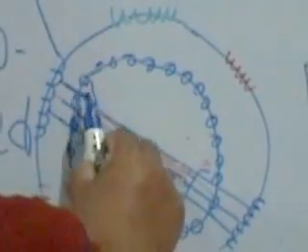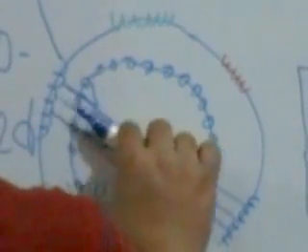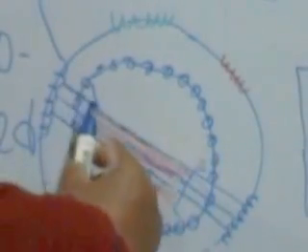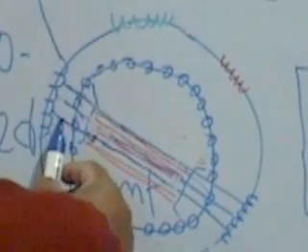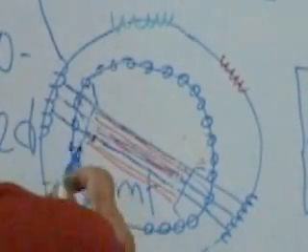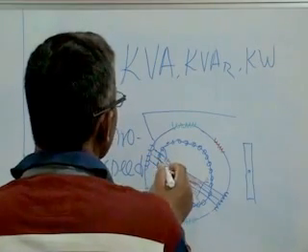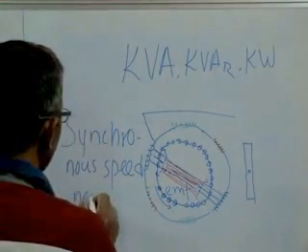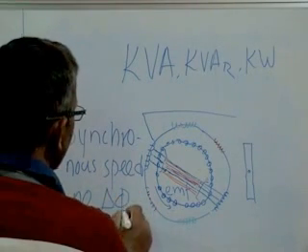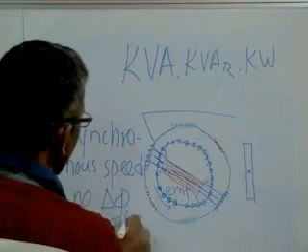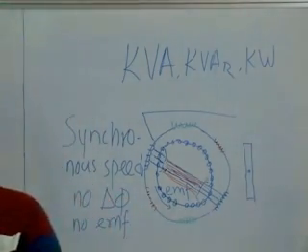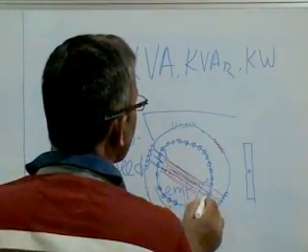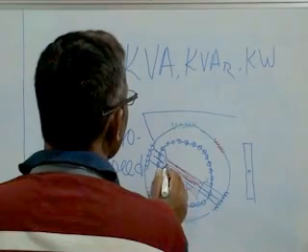In that case, there is no difference in speed of the two — that means there is no difference in speed of the stator magnetic field and the rotor magnetic field. When both speeds are the same, the stator magnetic field won't cut the rotor windings anymore. So there will be no change in flux in the rotor windings. If there is no change in flux, there will be no induced EMF. Once the EMF has dropped to zero, there will be no current in the rotor windings, and with no current the magnetic field of the rotor will vanish.